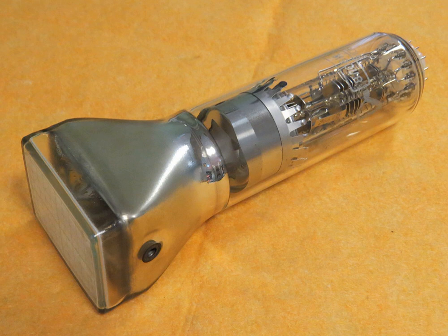Complete loss of signal in an XY CRT display means that the beam is stationary, striking a small spot. This risks burning the phosphor if the brightness is too high. Such damage was more common in older scopes, as the phosphors previously used burned more easily. Some dedicated XY displays reduce beam current greatly, or blank the display entirely, if there are no inputs present.